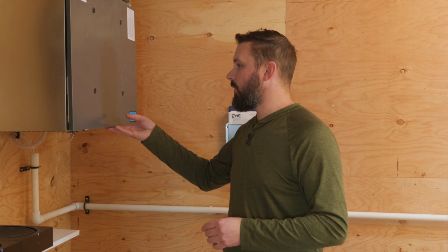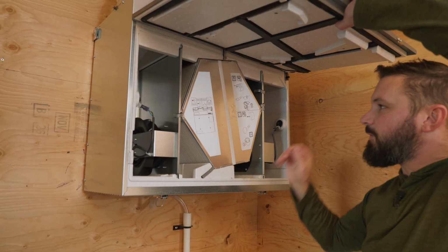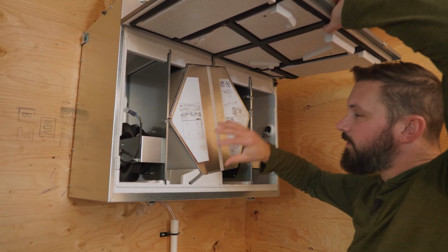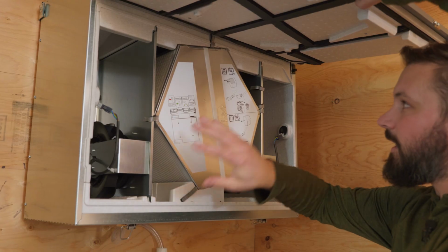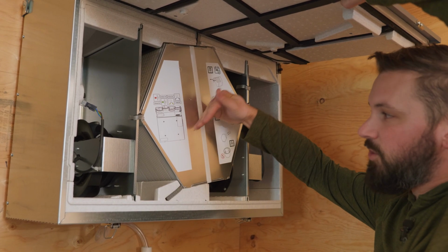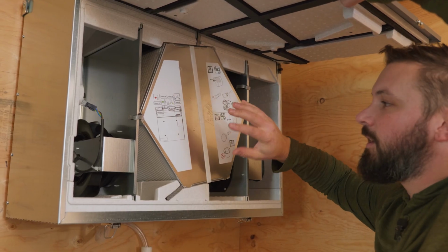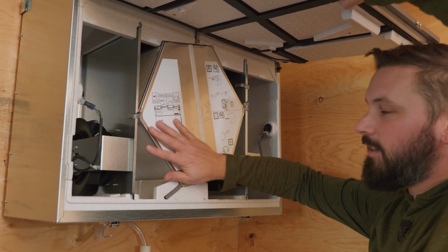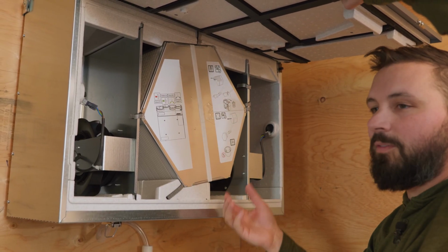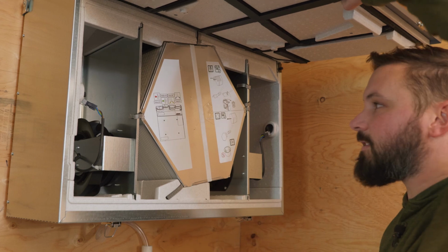That is the amount of energy that the HRV is able to take out of the outgoing air that it's exhausting to the exterior and put into the incoming air by exchanging it across a core. So on this HRV, you can see that we have a core inside here. This core is made of a bunch of little tubes that don't intersect but pass by each other. The incoming air from the outside gets passed through the core, and as it passes along adjacent to the tubes coming from the inside air, we exchange the energy between them. So the incoming air is heated or cooled by the outgoing air, allowing us to reduce the amount of energy that it takes to condition that air once it's inside the building envelope.